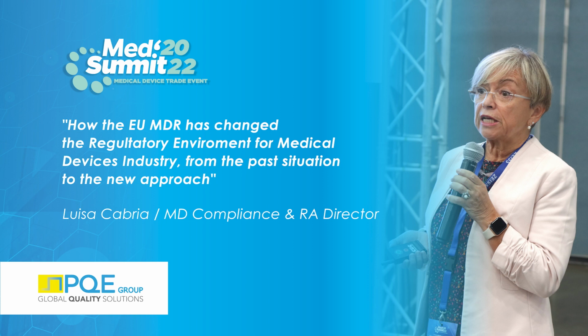Then there are specific requirements related to the characteristics of the product. For instance, the presence in the product of certain substances that are in direct contact with the body or with the blood. For these substances, the limit in terms of volumes is changed. That means that to be in compliance, to migrate to the new regulation, it is not sufficient to update the documentation, because there are devices that maybe were okay with the old directive, but maybe they are not in compliance with this requirement. For instance, for the presence of carcinogenic or mutagenic substances. So since the limit is changed, maybe your device cannot be distributed anyhow.